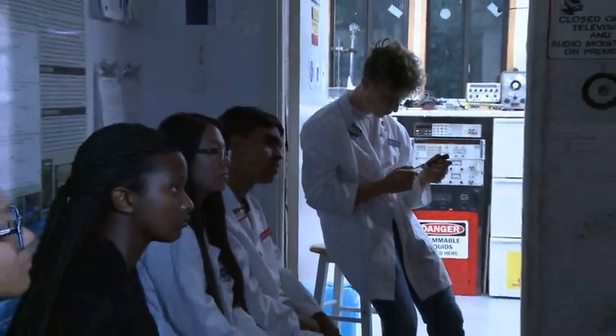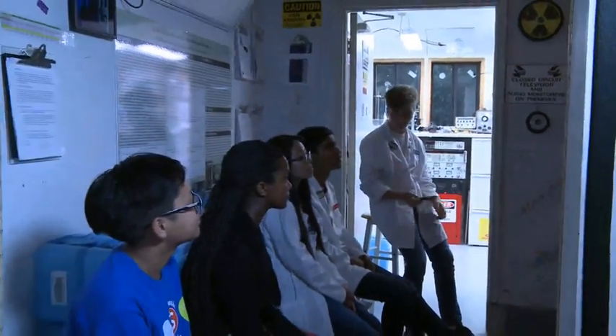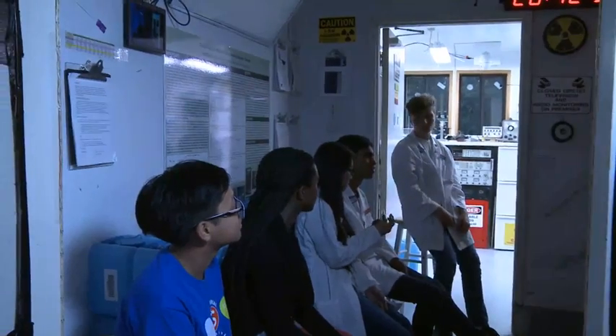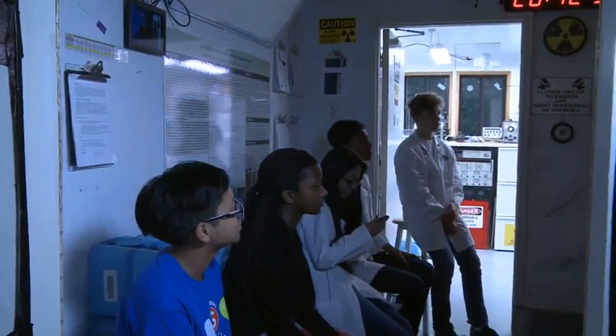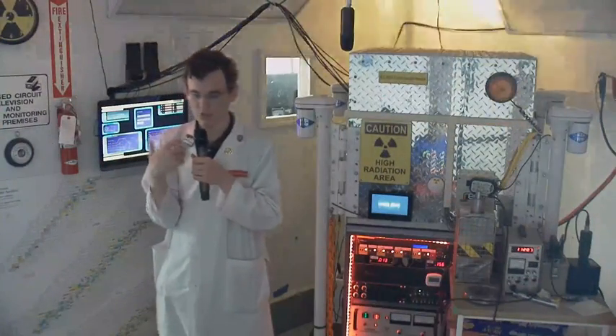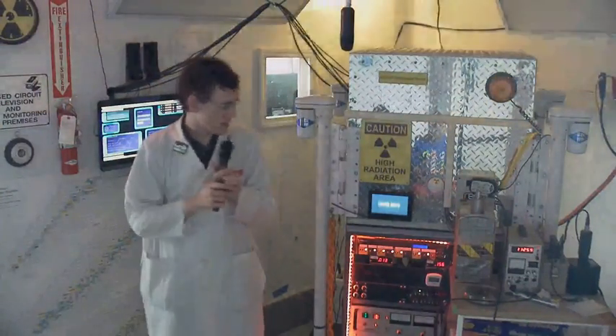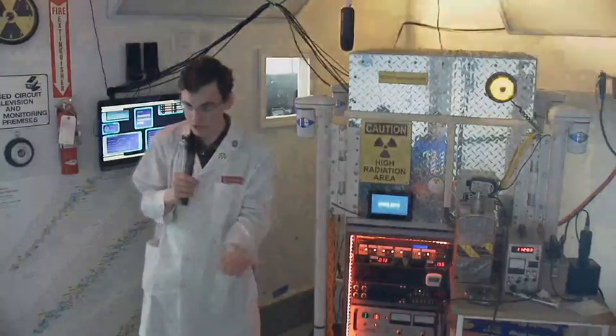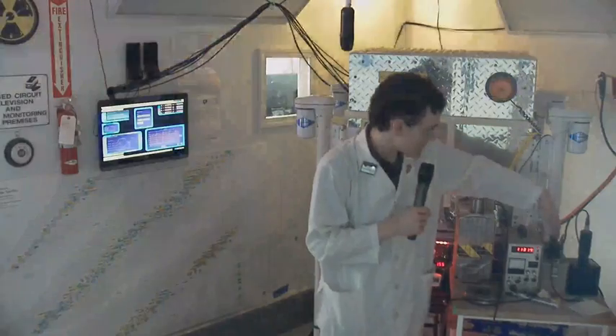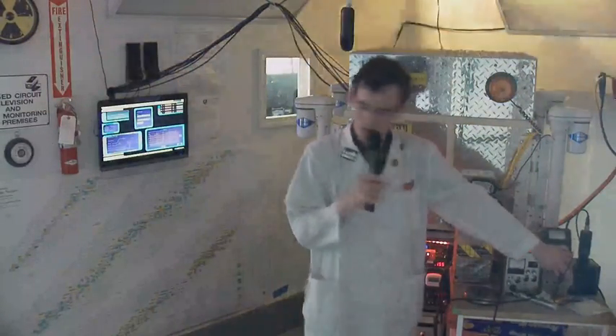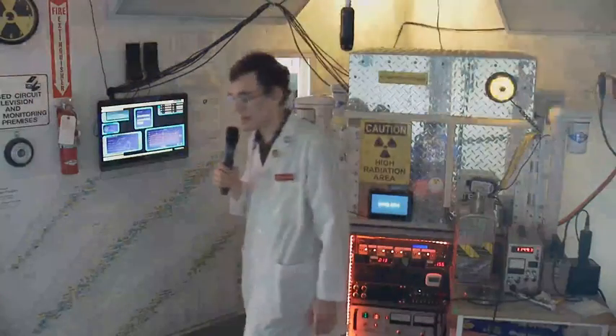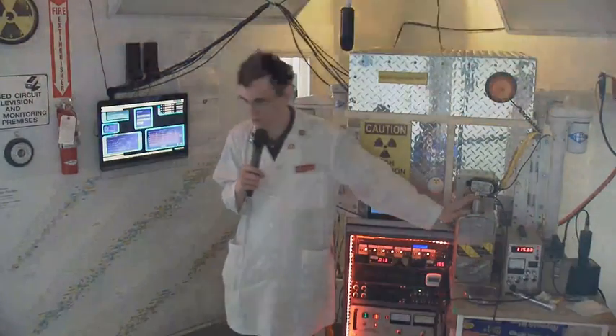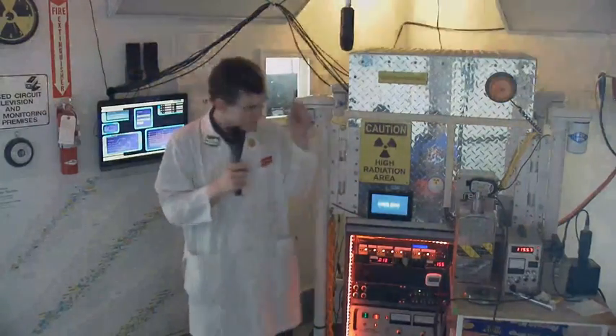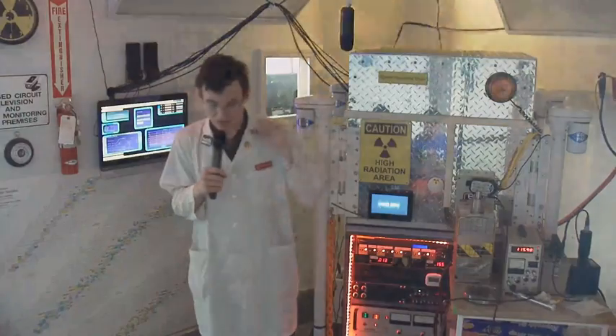Basically, what happens inside of this detector is the neutron comes in, and there's a special material in there that scintillates when it gets hit by a neutron. It produces a proton, something with a charge. And because the proton has a charge, that charge is detected by the counter right here. So this thing counts the number of protons that are freed by the neutrons that strike the detector and gives us an output. That's a very, very accurate way of measuring neutron output, much more accurate than the helium-3 tubes. It just gives you a count of how many neutrons are coming out, and it's great for that.